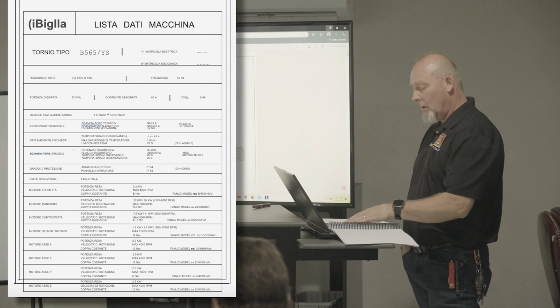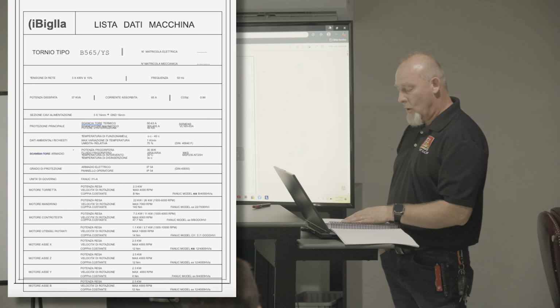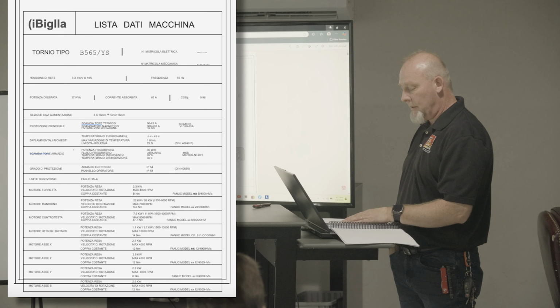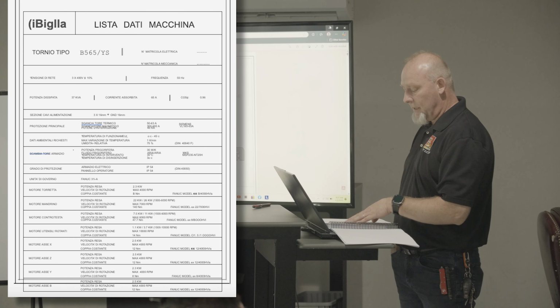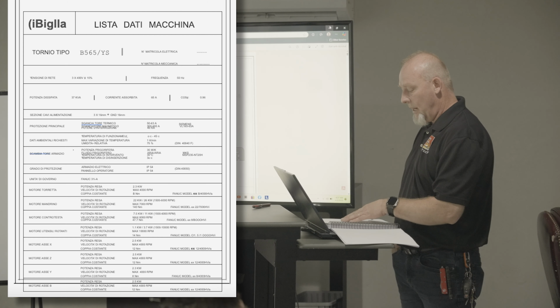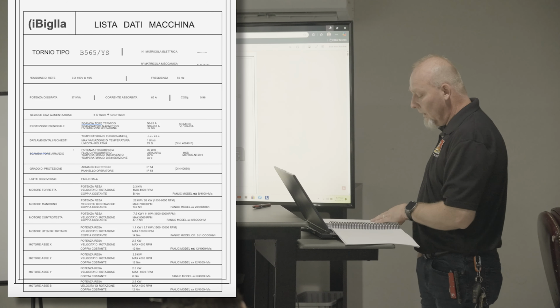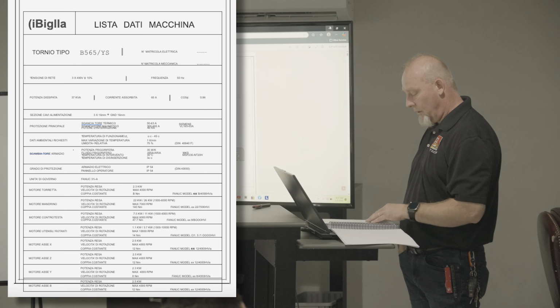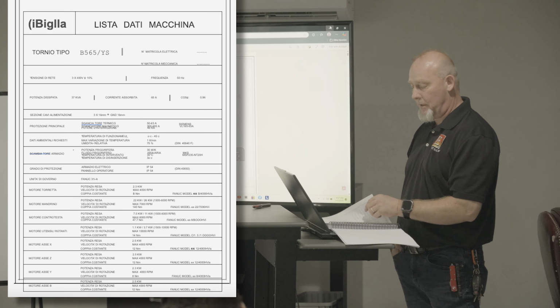So let's just go ahead and get right to the electrical manual and the flow. You guys as dealers get the machine, you got to deal with the customer, let them know what they need for power. So the very first page in your electrical schematics is going to tell you the three-phase voltage at 400 volts, three-phase at plus or minus 10% at 50 hertz. You're going to require a 37 kVA transformer, and then your current absorption. Below that you just have all of your drive and motor information.